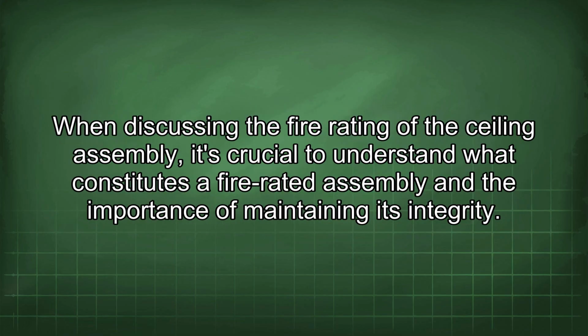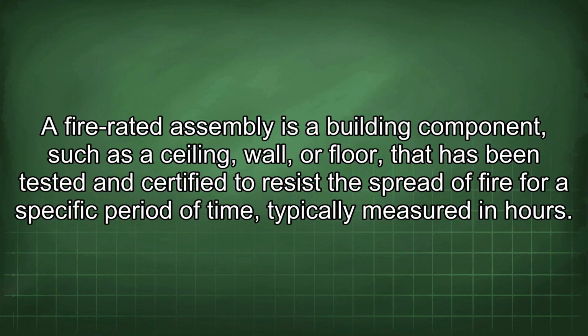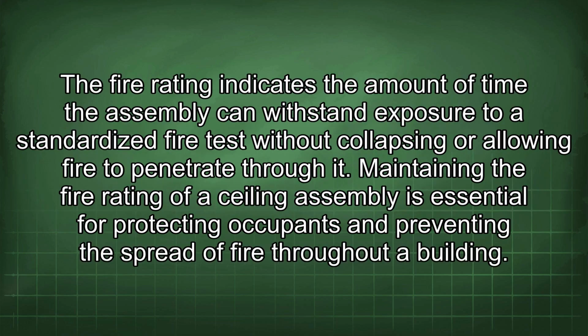When discussing the fire rating of the ceiling assembly, it's crucial to understand what constitutes a fire-rated assembly and the importance of maintaining its integrity. A fire-rated assembly is a building component such as a ceiling, wall, or floor that has been tested and certified to resist the spread of fire for a specific period of time, typically measured in hours. The fire rating indicates the amount of time the assembly can withstand exposure to a standardized fire test without collapsing or allowing fire to penetrate through it.